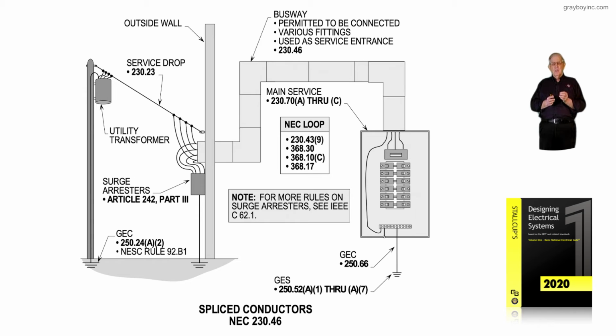But notice, in conjunction with Article 242, Part 3 for surge arresters, we are also recommending to you, based upon the type of arrestor used, to also review IEEE standard C62.1. Now, the grounding electrode system that is chosen is referenced in 250.52(A)(1) through (A)(7), where you would ground and bond all of the electrodes that are present into an electrode system in accordance with 250.50. Now, one other thing I would call your attention to.